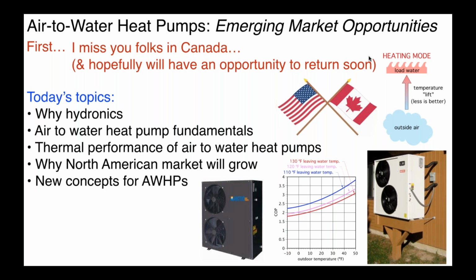In the winter, they take heat from outside air by using a refrigeration circuit, and they put that heat into a stream of water, or it could be a mixture of water and antifreeze, and that's what goes in and heats the building. So we're configuring a heat pump to gather heat from outside air, as opposed to, let's say, from a geothermal earth loop or a pond or a lake. And we're also configuring that heat pump to interface with a modern hydronic distribution system. We'll take a look at the thermal performance of those heat pumps. What are the parameters that affect the heating capacity, the cooling capacity, and the efficiency of the heat pump?